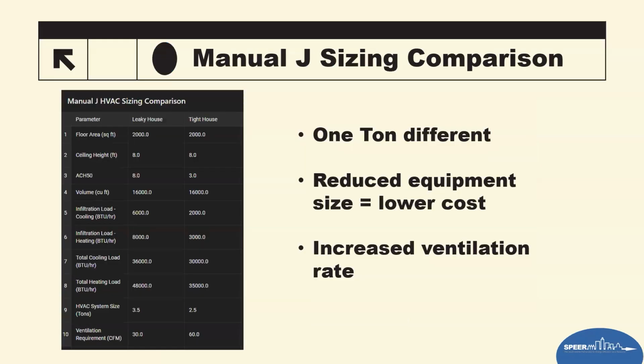So here's another comparison of a leaky house versus a tight one. This is assuming a 2,000 square foot home. As we can see here, 2,000 square feet, 8-foot ceiling height. The leaky house is 8 ACH and the tight is 3 ACH. The volume is the same, roughly 16,000. Now we have 6,000 BTUs of cooling due to infiltration on the leaky house and 2,000 on the tight. Same for heating. We have much higher BTUs per hour than it would be if it was a tight home. If you go all the way to the bottom, now you're seeing that the HVAC system size is 1 ton oversized.